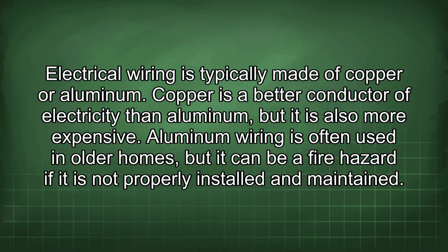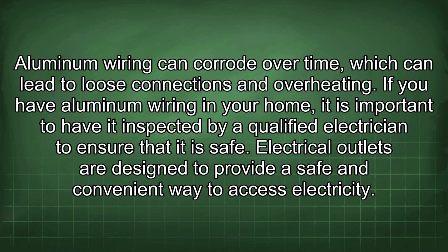Electrical wiring is typically made of copper or aluminum. Copper is a better conductor of electricity than aluminum, but it is also more expensive. Aluminum wiring is often used in older homes, but it can be a fire hazard if it is not properly installed and maintained. Aluminum wiring can corrode over time, which can lead to loose connections and overheating. If you have aluminum wiring in your home, it is important to have it inspected by a qualified electrician to ensure that it is safe.